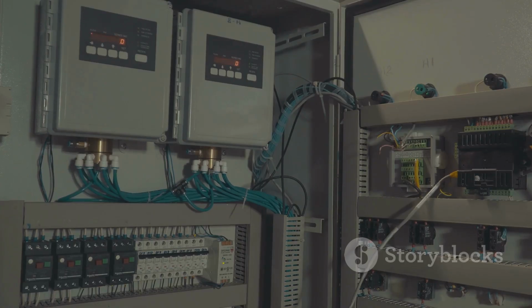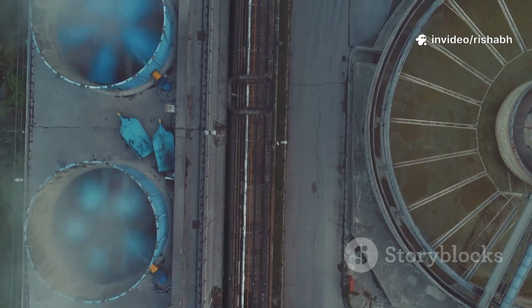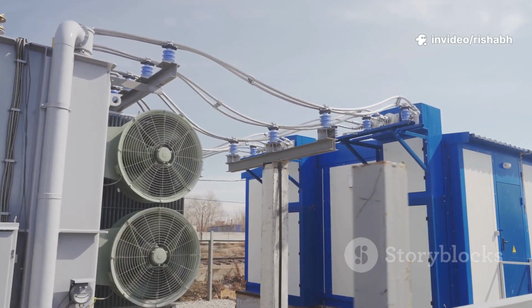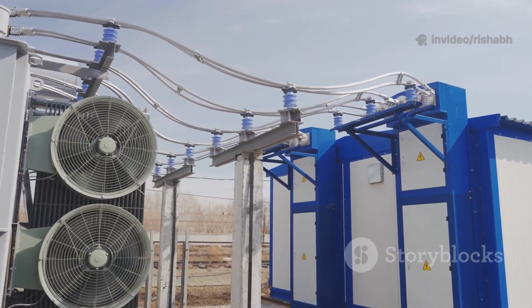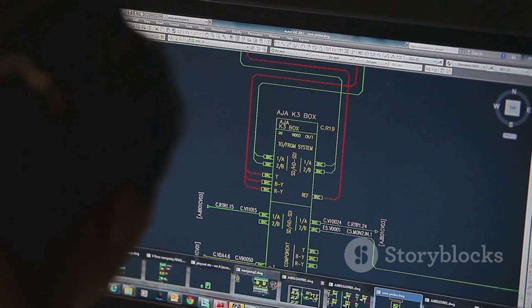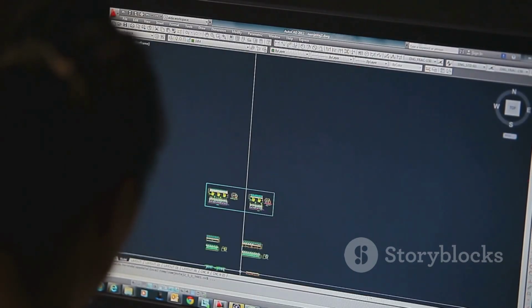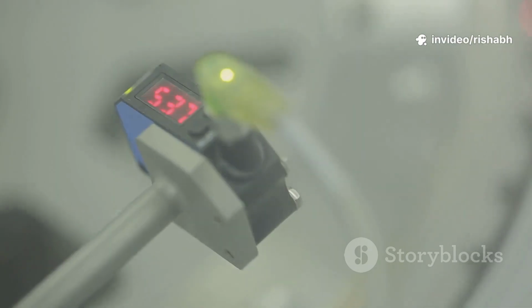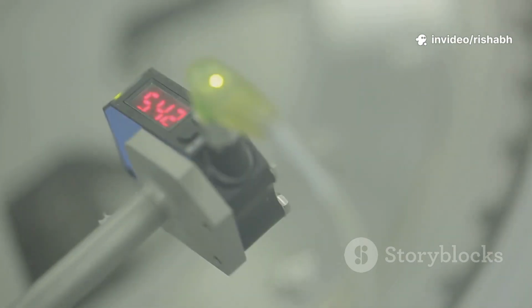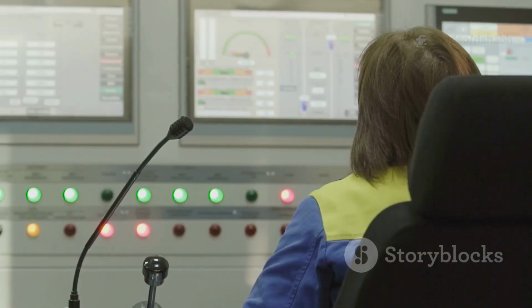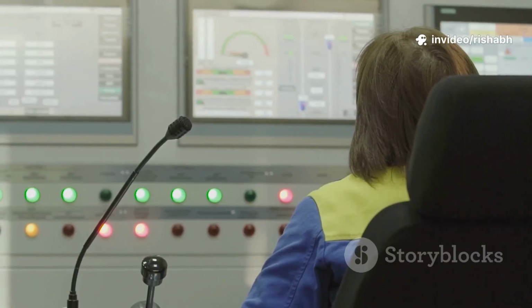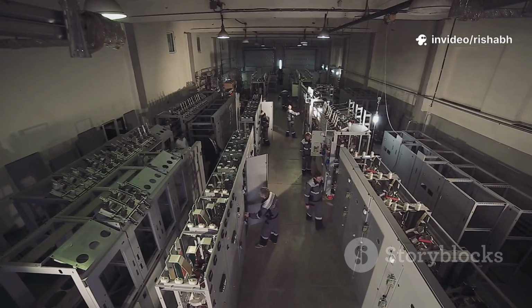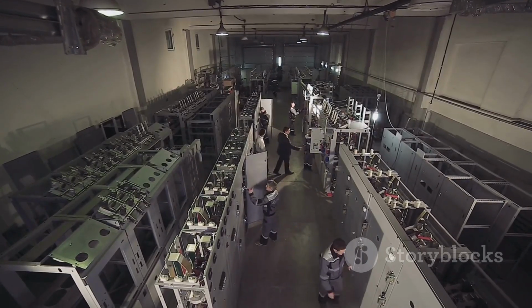Then there's the thermal model, which protects against overheating. Transformers generate a lot of heat during normal operation. They have cooling systems with fans and oil to manage this, but sometimes things can go wrong. The Multilin 845 doesn't just measure the temperature directly, it builds a sophisticated thermal model of the transformer. It uses information about the electrical load, the ambient temperature, and the cooling system status to calculate the internal temperature of the transformer's windings. If it predicts that the windings are getting dangerously hot, it can trigger an alarm or, if necessary, take the transformer offline to let it cool down, preventing long-term degradation.